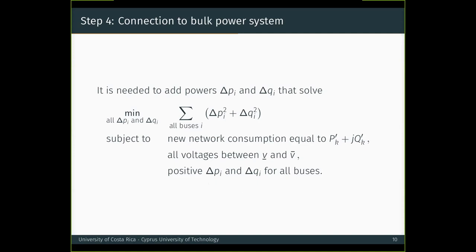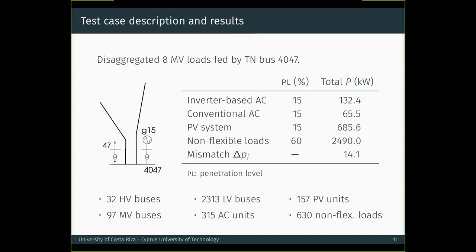We then applied this four step methodology to a transmission distribution system and in this way come to our results. We disaggregated eight medium voltage loads fed by transmission bus 4047. And we allocated inverter based and air conditioning and conventional air conditioning units, PV systems and non-flexible loads with the penetration levels shown in the center column and that amounted to the powers shown on the right. It's important to note that this system, only by disaggregating eight medium voltage loads, we had more than 2300 low voltage buses.